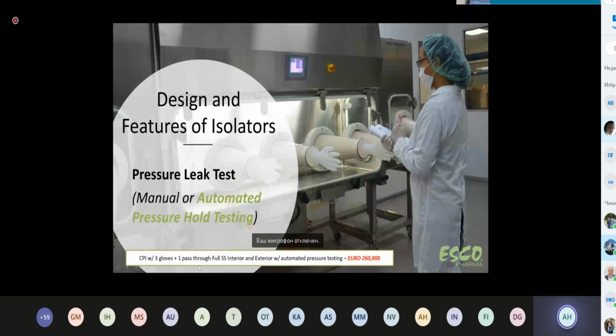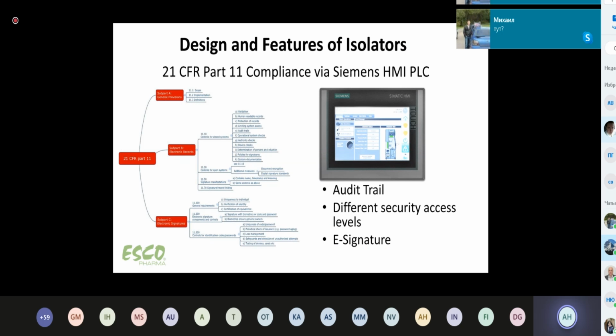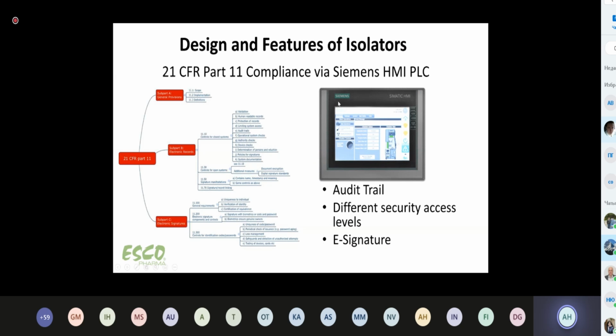Next, the second feature of CPI is that we use a Siemens HMI PLC. We must understand that accountability, security, and traceability are the common words that are the focus of GMP. So there is a requirement called 21 CFR Part 11 that must be met by the software of the isolator. There are a few things we have to look at, but basically the Siemens HMI PLC does the job very well. There are a few things that will be asked for by the customer. The audit trail, I will show you.